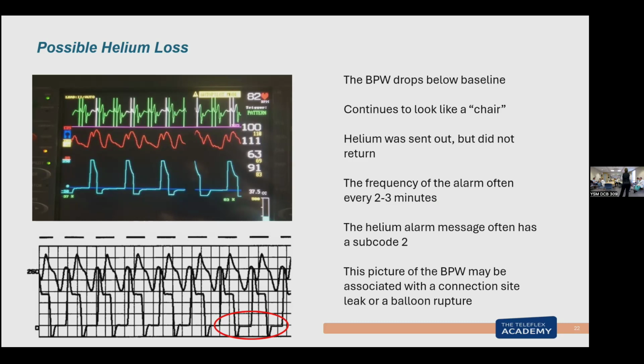I just know that the pump is pushing it in, pulling it out, and I'm expecting 40 to come back, and it didn't get 40 back. These are red or yellow, and a not functioning pump at that point. What's that? That's red or yellow. Red. And so it's not working. It'll stop pumping. It says there's something that you need to troubleshoot now.